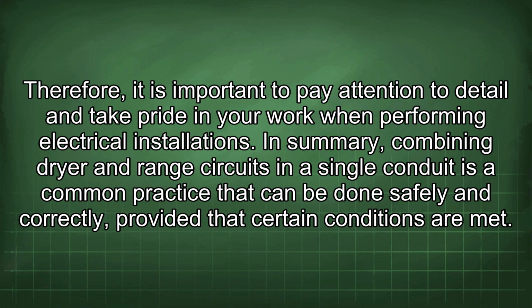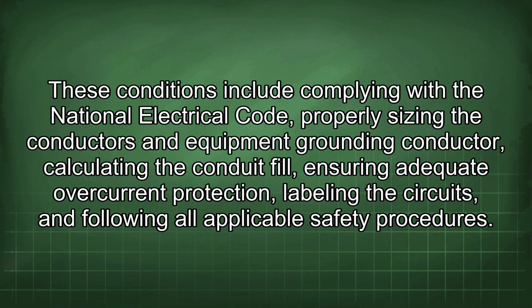In summary, combining dryer and range circuits in a single conduit is a common practice that can be done safely and correctly, provided that certain conditions are met. These conditions include complying with the National Electrical Code, properly sizing the conductors and equipment grounding conductor, calculating the conduit fill, ensuring adequate overcurrent protection, labeling the circuits, and following all applicable safety procedures.